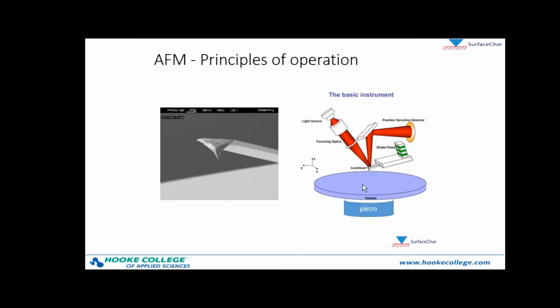And then in this configuration of the instrument, we have a piezo that's positioned underneath the sample that's going to move the sample around in X and Y, and the cantilever will interact in a variety of ways as the sample is scanned, and then we track the motion of the lever with this laser or optical beam. So that's the general principle of operation. And to first order, you can use that to map the topography as we've discussed.